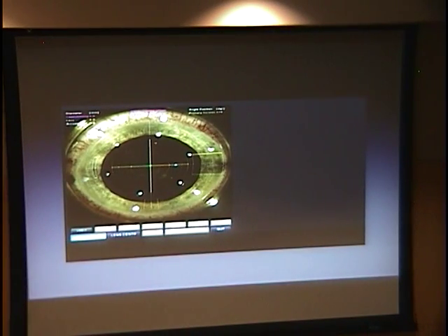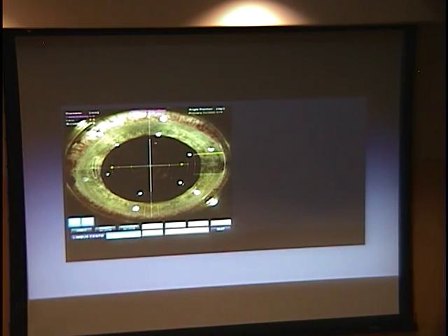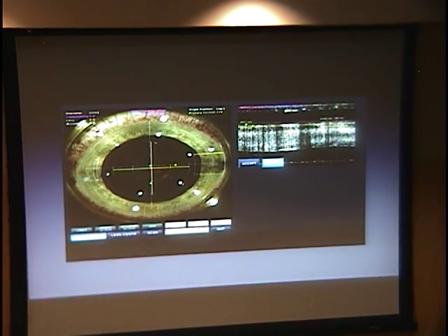And then the other part, for those that haven't seen, let me just show you what it looks like. This is an eye that's been docked. This is with the older software. It's going to take about 12 to 14 seconds to do the rhexis, which is now down to five to six seconds in this machine.